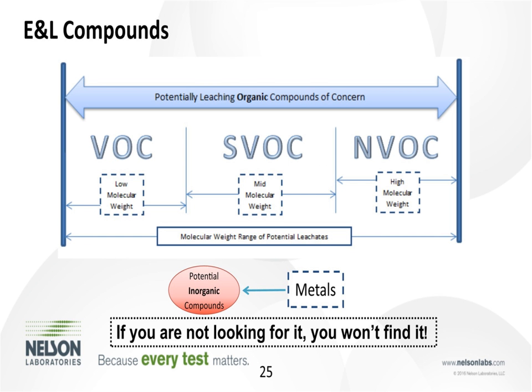So I mentioned this wide net. We're going to cast this really wide net and look for essentially anything that could come off of the device. So we're looking for things like volatile organic compounds, semi-volatile organic compounds, and non-volatile organic compounds. Also, we want to look for some inorganic compounds, specifically metals. Now, unfortunately, this is not as easy as the TV show CSI portrays.